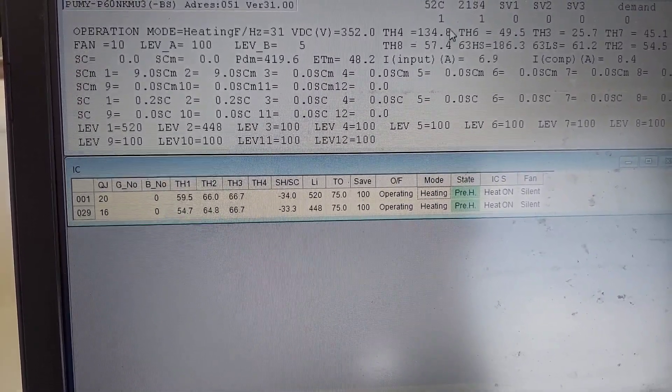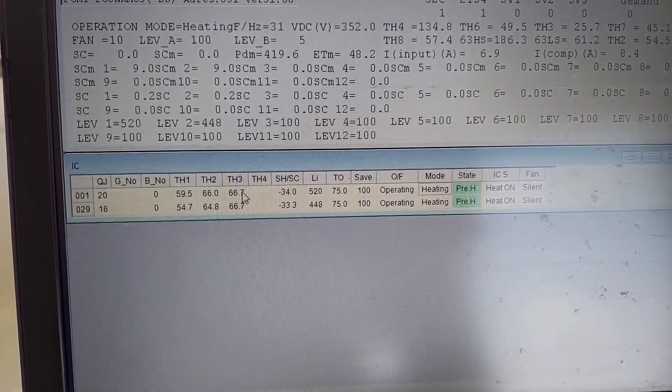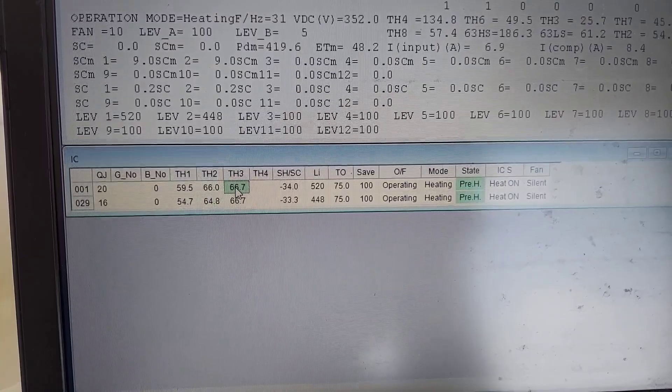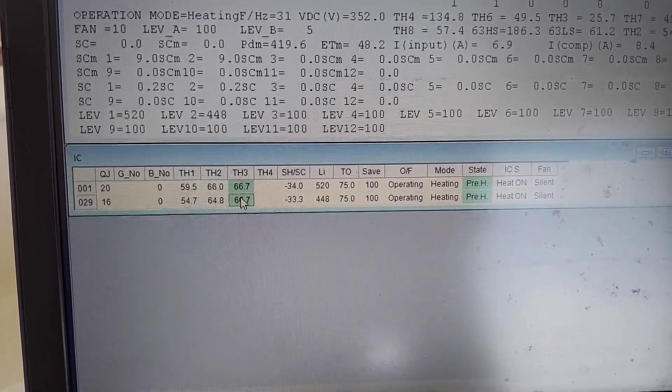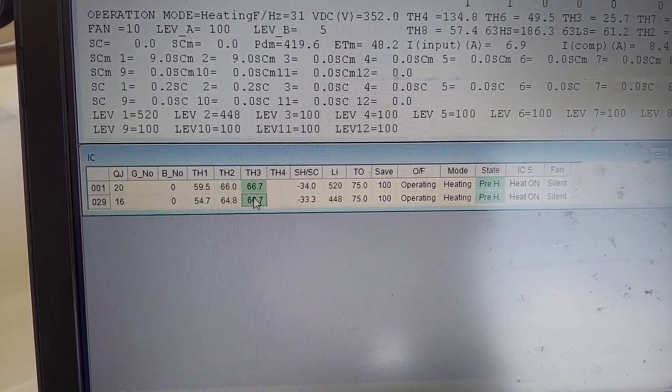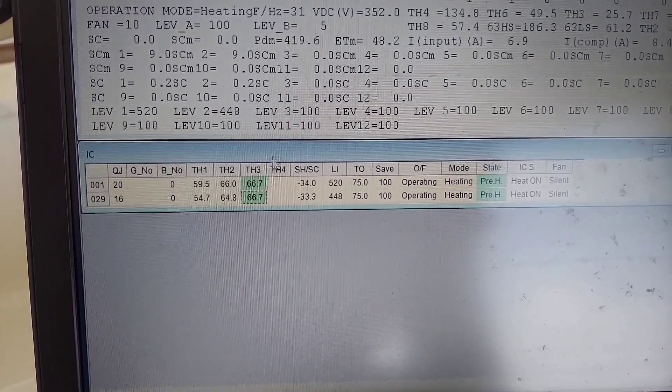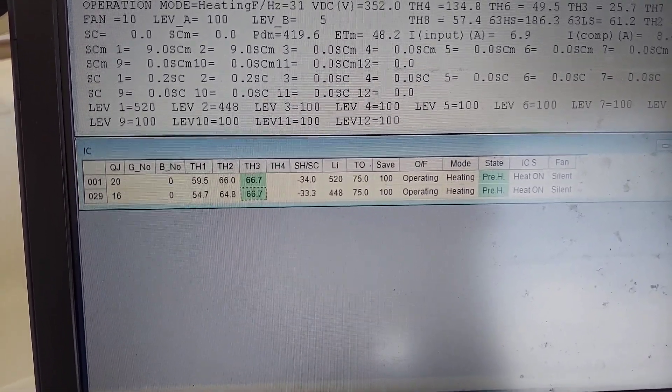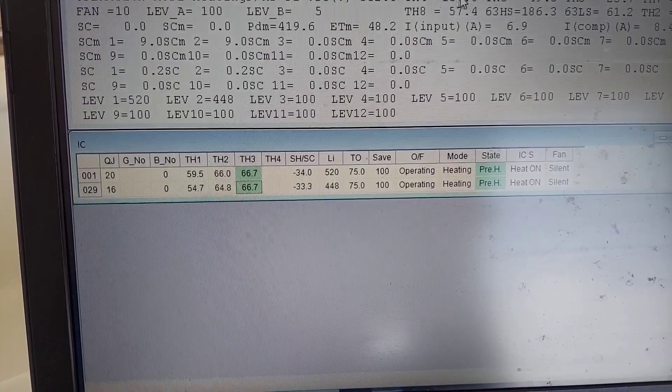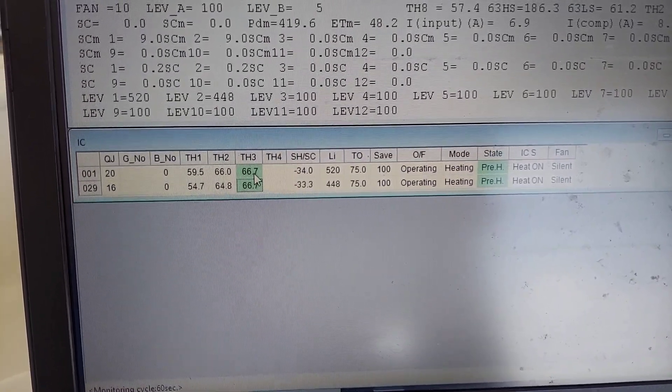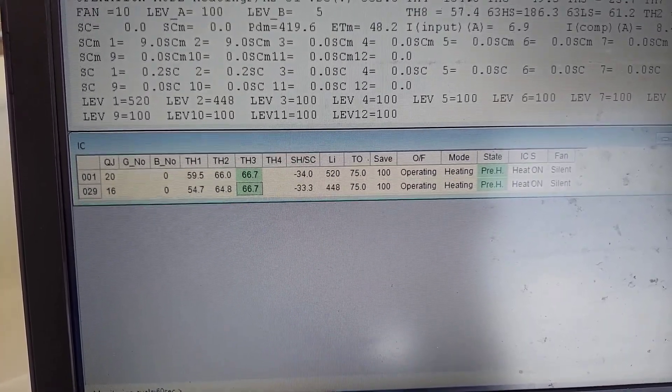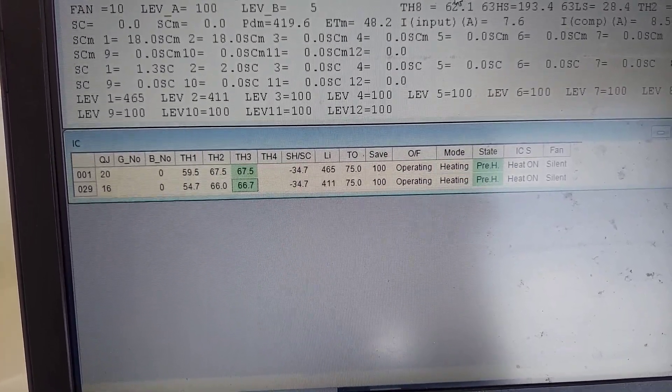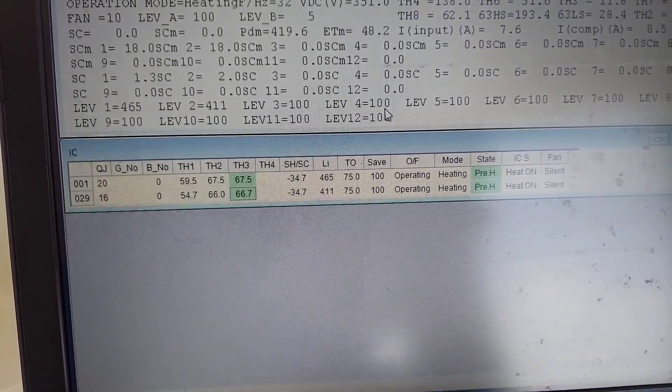Compressor discharge pipe right here and these are the pipes coming into the indoor units, you know, after it traveled for how many feet between the indoor and the condenser. But yeah, you know, this number here and this number here, two four apart. So I know this is mostly heat of compression most likely.